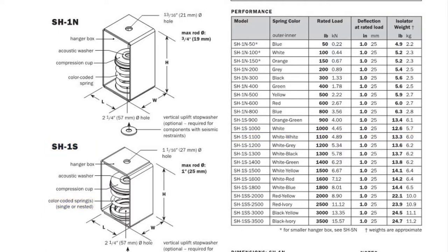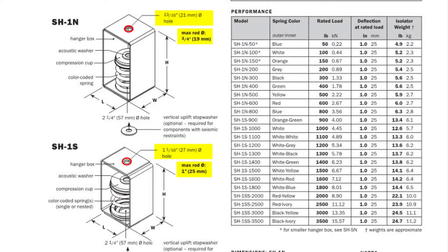While we're here I want to point out that the N boxes have 13/16 inch holes in the top of the hanger boxes and the S boxes have 1 and 1/16 inch diameter holes. These are sized to accommodate hanger rods up to 3/4 inch and 1 inch respectively.